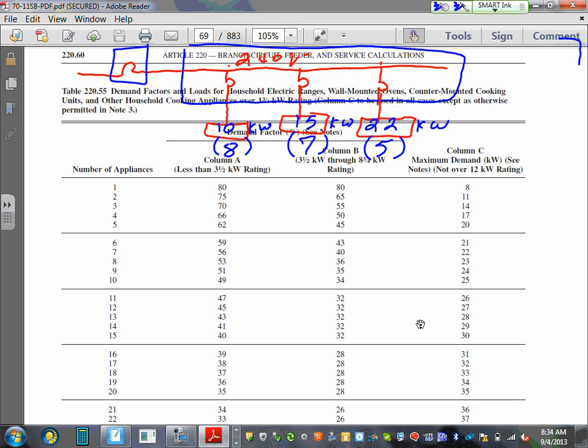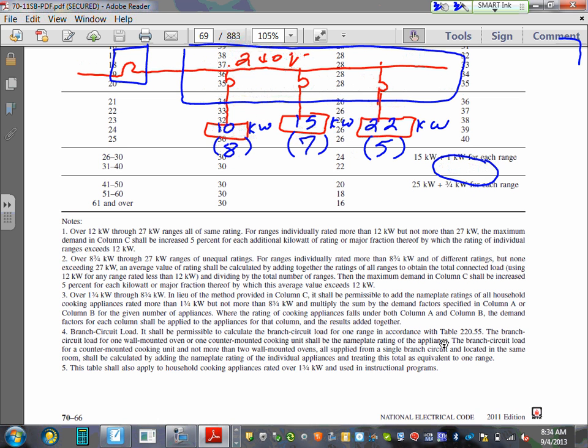So look at this system. Let me ask you this. Look at the sizes. Is any one of them size-wise under A or B to start with? Think 15 kW and 22 kW. No. So forget about applying A or B from the get-go. Are they all not over 12? No, they are more than 12. So if they're over 12, then you're going to apply the rule down here. The rule down here is, I'm going to highlight it right in here.